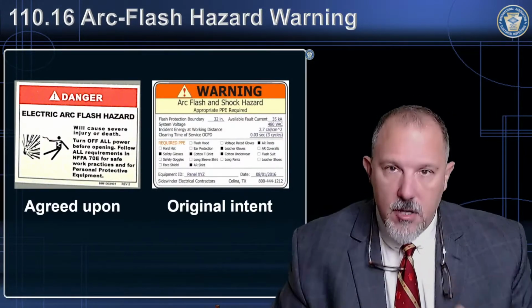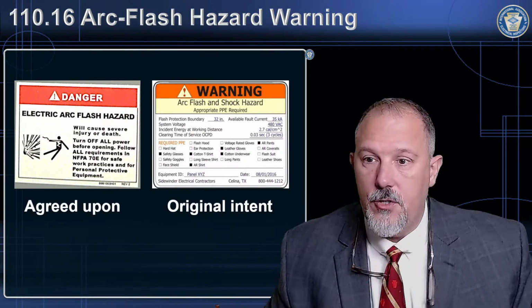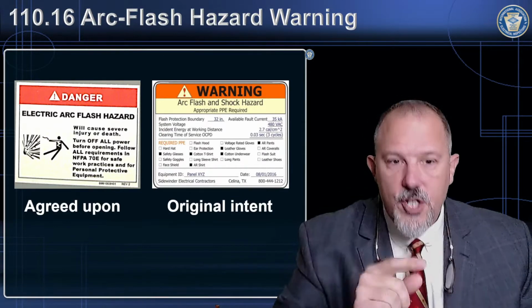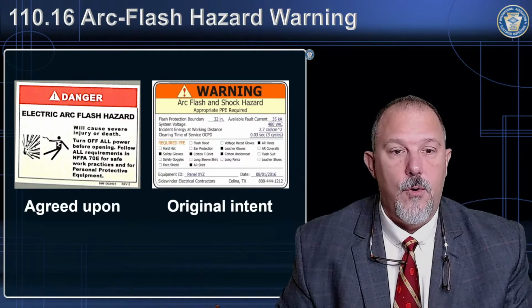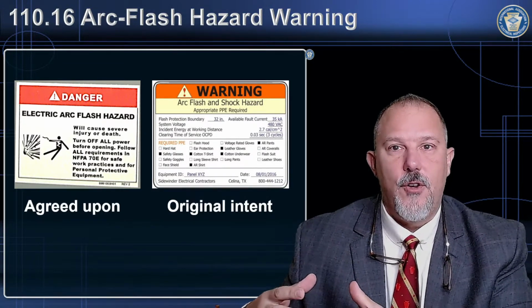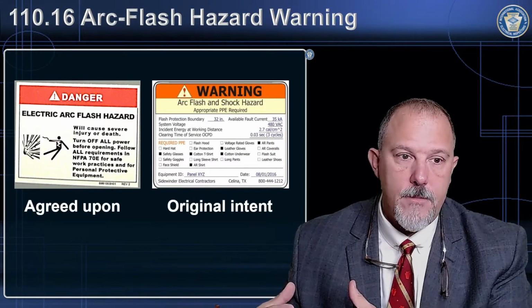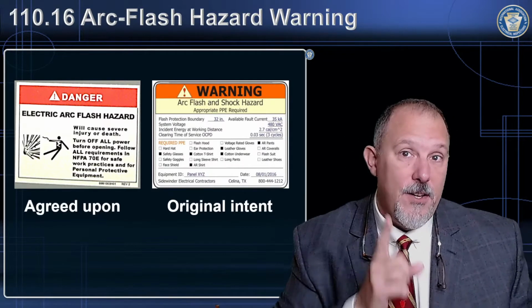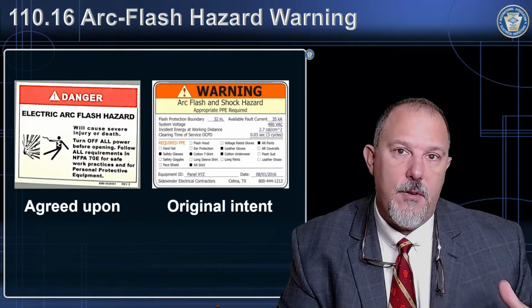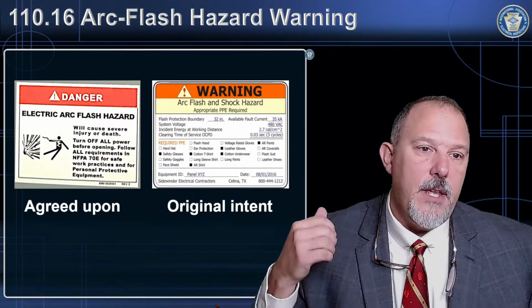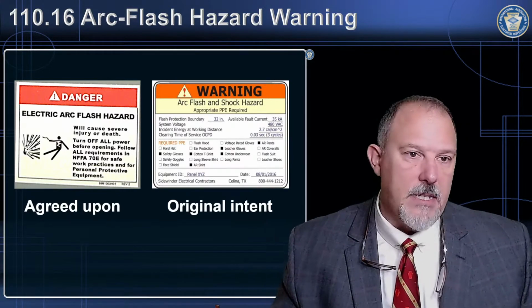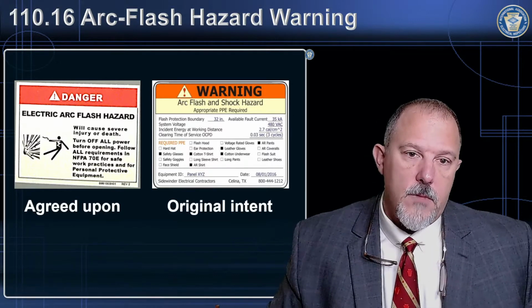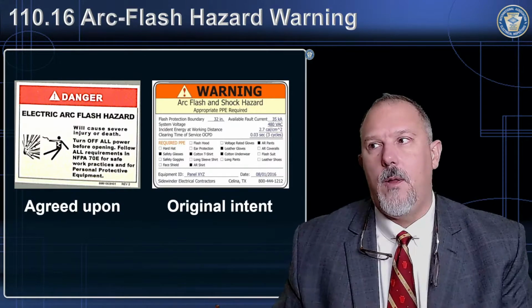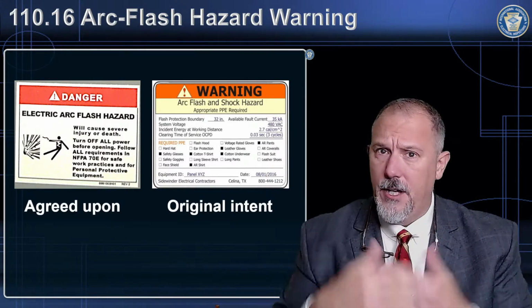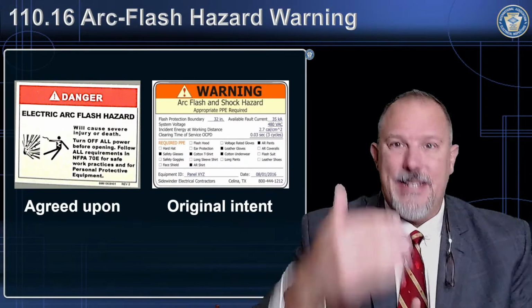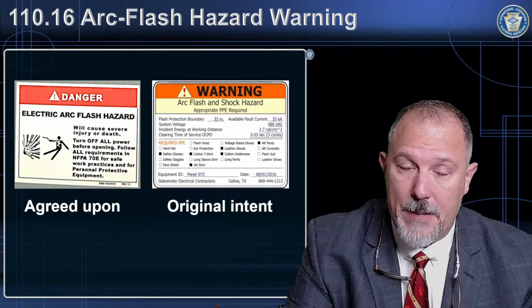Now, if I look back at the history of 110.16, which we're going to do together, the original intent of the submitter was to create an arc flash incident label for equipment with incident energy. What was eventually agreed upon in the first edition, which I'm not going to tell you the year, the first edition of the code that required 110.16, was the standard arc flash hazard label that just basically says you can get hurt. They started off with more of what I would call a 70E label. Calories per centimeter squared is how we measure the heat, along with the working distance and the arc flash boundary. And we're going to talk about 70E.